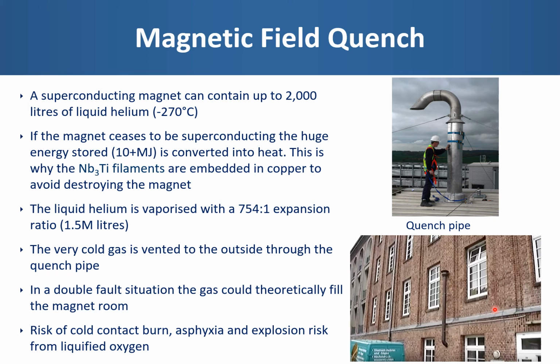As we've already discussed, the helium gas is extremely cold and therefore there are risks of cold contact burns. Helium displaces oxygen, so there is also a risk of asphyxia, and there is also a potential explosion risk because the temperature is cold enough to liquefy oxygen from the air.